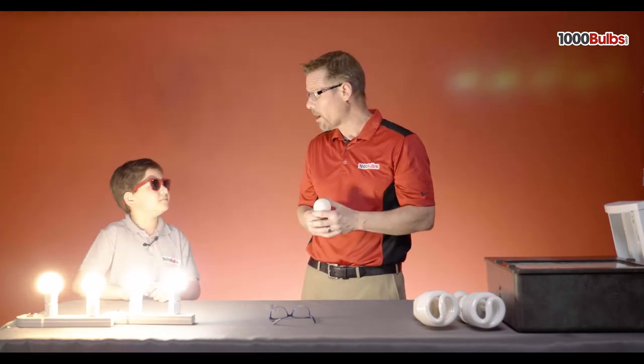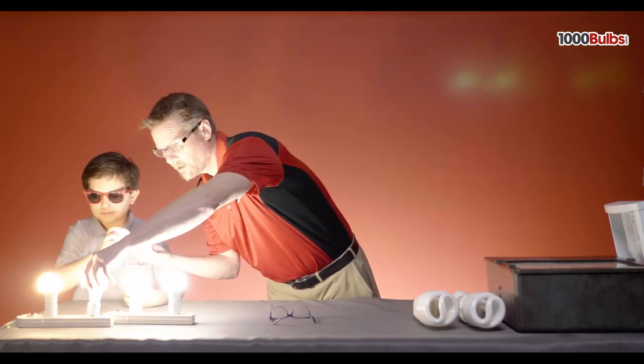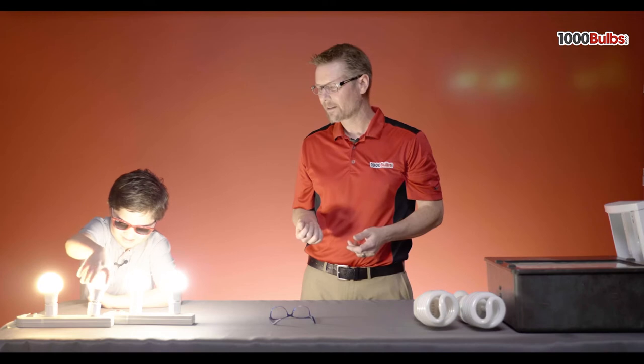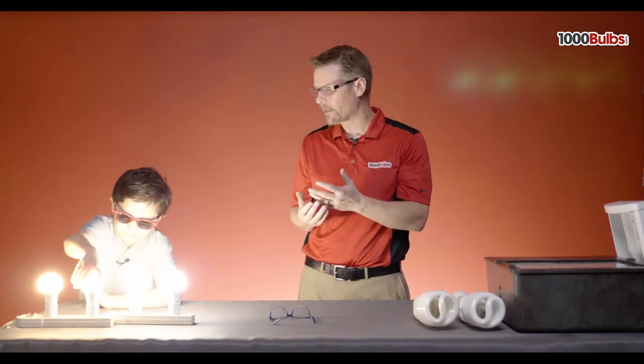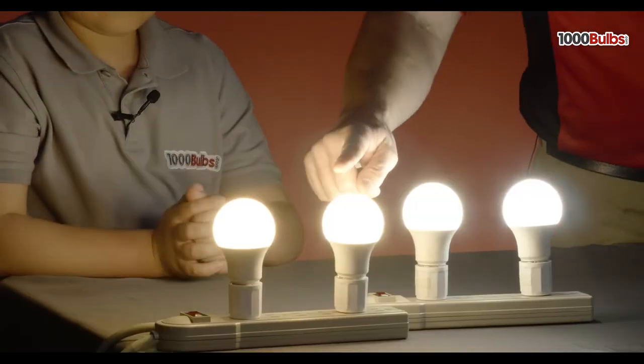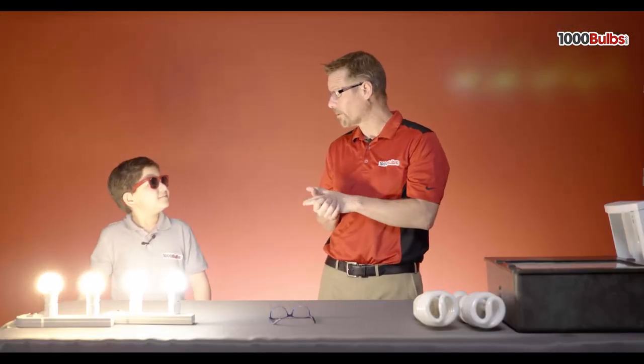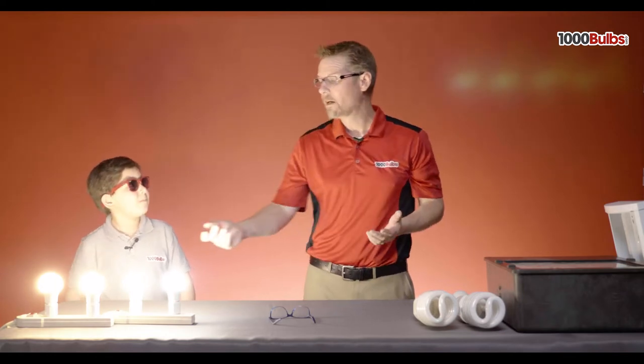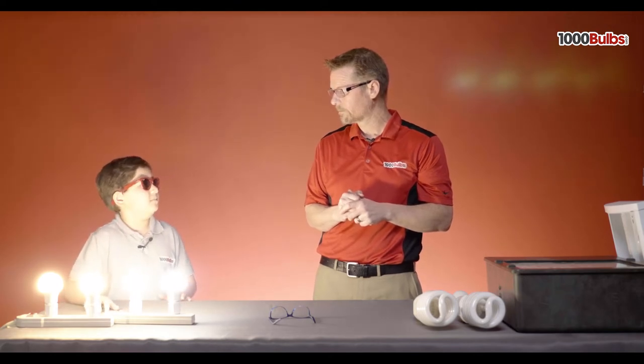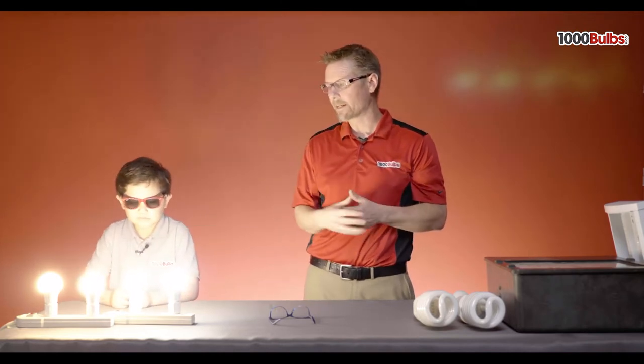Something people watching may not know is that the incandescent light bulb is close to 2,700 Kelvin. And halogen light bulbs, if you didn't know, are closer to 3,000 Kelvin — because halogen has voltage going through a tungsten filament and it's a lot thicker. So if you had a PAR lamp like a 50-watt PAR 20, that would have a 3,000 color temperature. And it was considered whiter than incandescent — it was actually a step up.